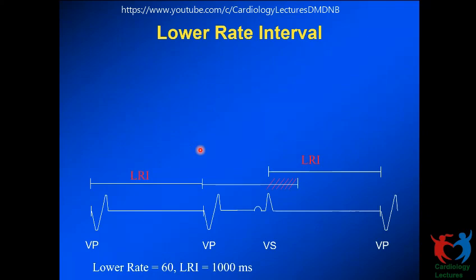In a single chamber ventricular pacemaker, the lower rate, in this case, we program 60 beats per minute, which corresponds to an RR pacing interval of 1000 milliseconds. The pacemaker delivers the V pace, starts the clock of 1000 milliseconds and delivers the next V pace. And it starts the clock all over again. Along the way, it finds one ventricular intrinsic event happening, which is sensed by the pacemaker, and it calls it a V sense. V pace is called a VP. Then it resets the clock back to 0, starts the lower rate interval and delivers a V pace here. So my lower rate interval is V pace to V pace or V sense to V pace.